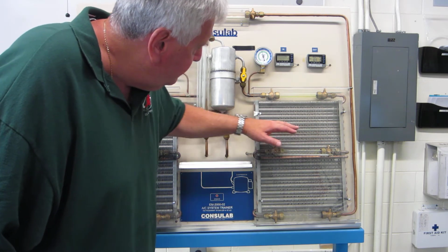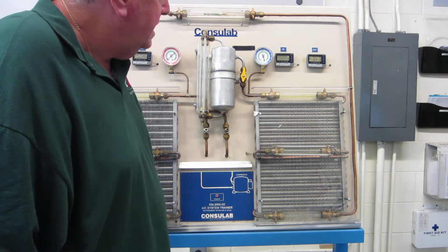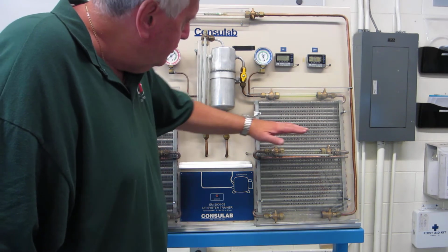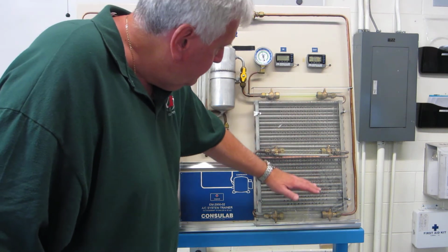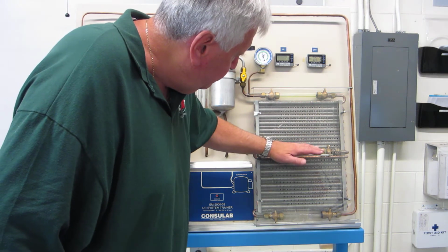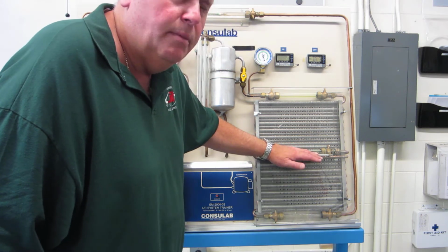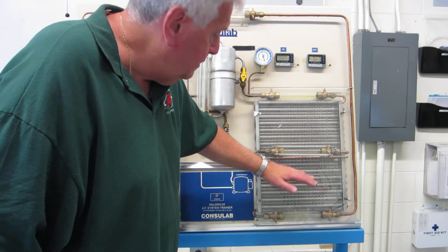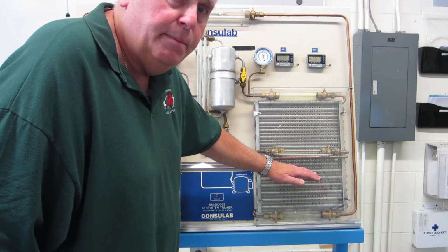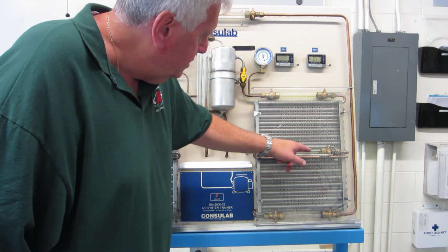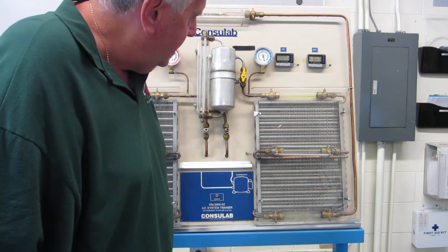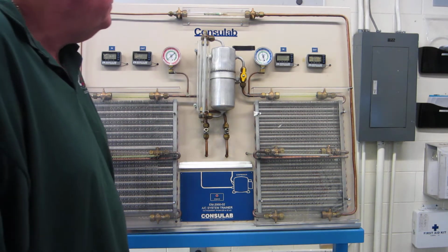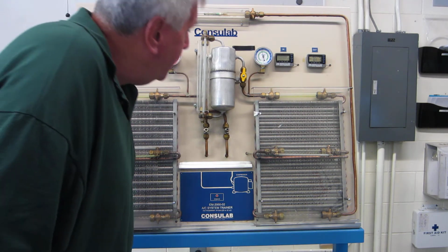Again, now we'll continue back and forth through here, and we're going to gain some heat energy after we've gone through the state of change. So in other words, we're going to gain some superheat. Remember, my greatest exchange of heat energy takes place from my inlet to my latent heat of evaporation, also referred to as hidden heat. The reason we refer to it as hidden heat is there is no temperature change. We don't know it's gained heat energy. The only way we know we've gained heat energy is by the fact that it's changed states. So now coming out of the evaporator, should have a low temperature, low pressure vapor.